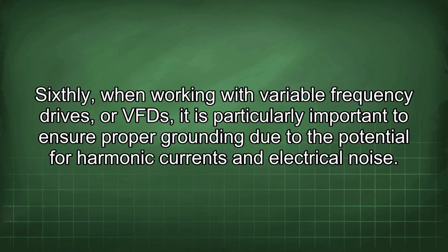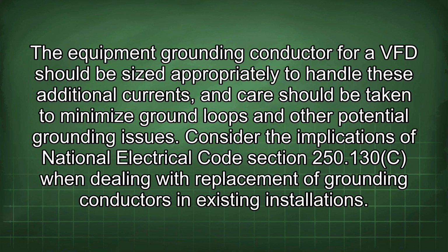Sixthly, when working with variable frequency drives, or VFDs, it is particularly important to ensure proper grounding due to the potential for harmonic currents and electrical noise. The equipment grounding conductor for a VFD should be sized appropriately to handle these additional currents, and care should be taken to minimize ground loops and other potential grounding issues. Consider the implications of National Electrical Code Section 250.130(C) when dealing with replacement of grounding conductors in existing installations.